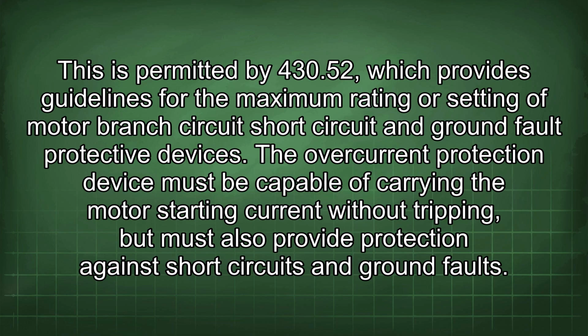This is permitted by 430.52, which provides guidelines for the maximum rating or setting of motor branch circuit, short circuit, and ground fault protective devices. The overcurrent protection device must be capable of carrying the motor starting current without tripping, but must also provide protection against short circuits and ground faults.